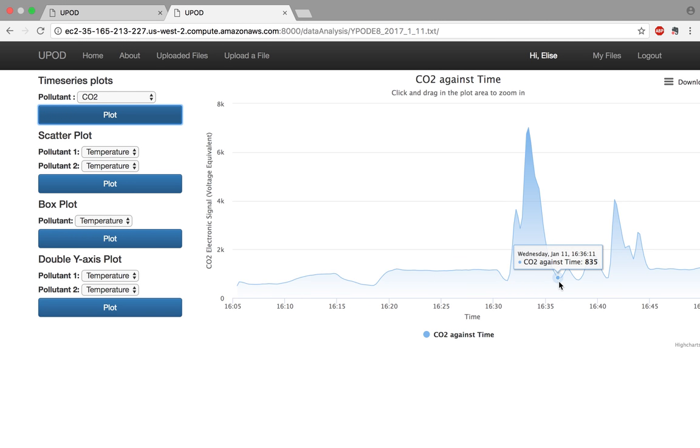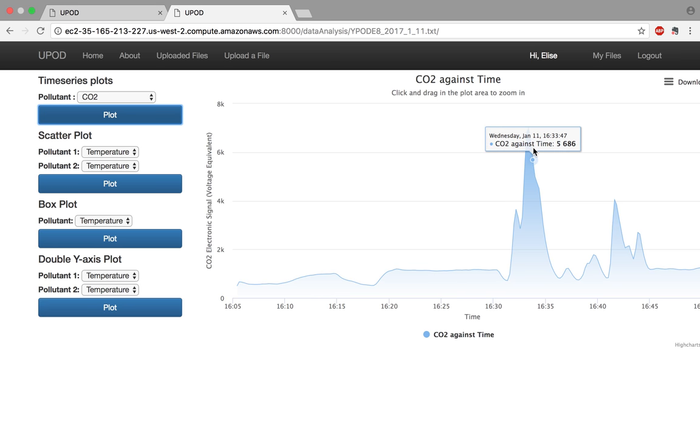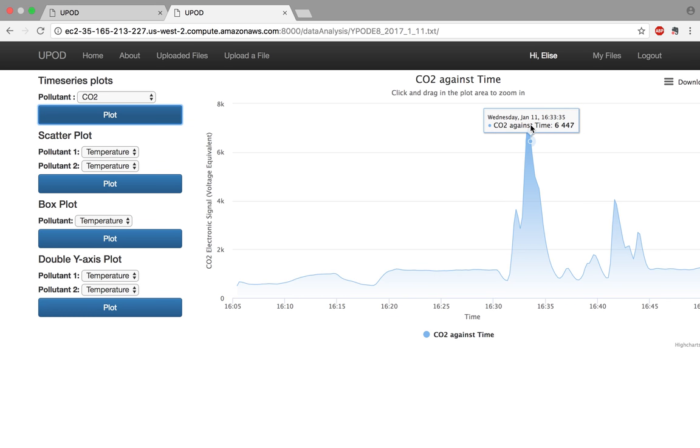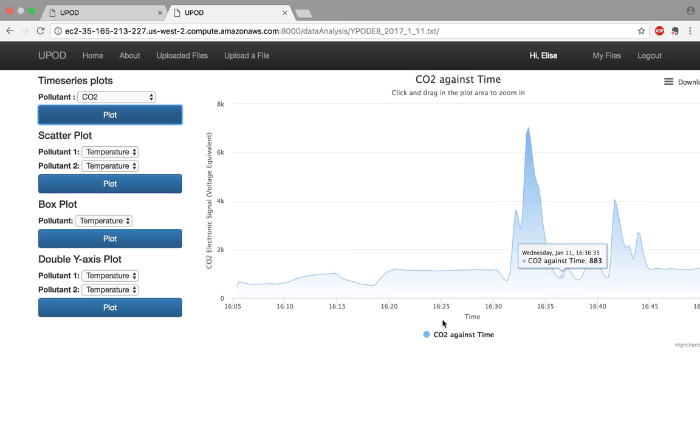So when using the raw signal you can only use this to compare the amount of pollutant exposed to the pod. So at the peaks, you have more pollutant exposed to the pod than at the valleys, but you can't say anything about how much concentration the pod was exposed to.